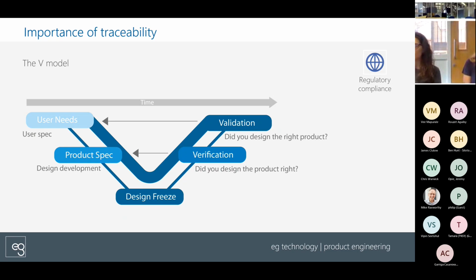If you wanted to divert from this, you'd have to have a very good reason and be able to argue your case with auditors. And what this diagram is really saying is that you start with user needs, you trace that down into defining your product specification, you use that to design your product, and then back up on this other side when you're verifying, you need to verify against your product requirements, and then keep tracing that back up to your validation, and you validate against your user requirements. And the key difference here between verification and validation, and therefore between product requirements and user requirements, is that when you're verifying, you're asking, did you design the product right? Whereas in validation, you're asking, did you design the right product?